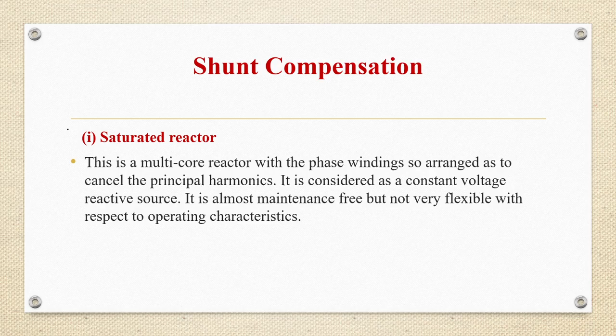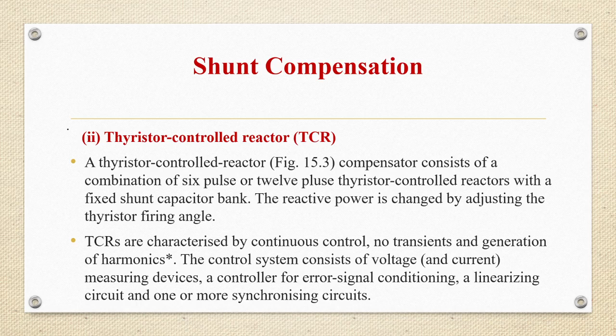The second one is the thyristor controlled reactor (TCR). A TCR compensator consists of a combination of 6 pulse or 12 pulse thyristor controlled reactors with a fixed shunt capacitor bank, as shown in this figure. Reactive power will be changed by adjusting the thyristor firing angle. Thyristor controlled reactors are characterized by continuous control, no transients and generation of harmonics. The control system consists of voltage and current measuring devices, a controller for error signal conditioning, a linearizing circuit, and one or more synchronizing circuits.